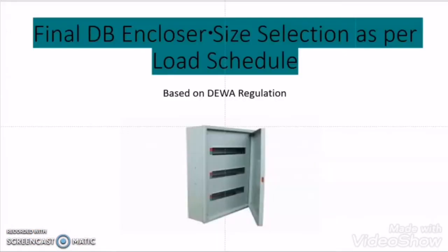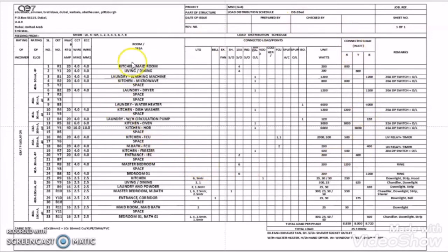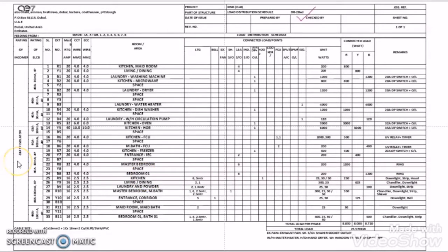Now let us get back to our original topic — how to select the final distribution board enclosure as per the load schedule. To better understand this topic, let us take an example. This is the load schedule for a two bedroom flat final distribution board. The incomer of this final distribution board is a 63 ampere triple pole isolator, which is equivalent to three modules.